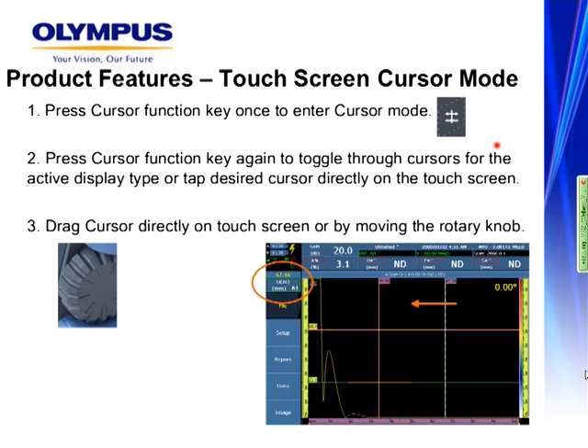In addition to the touchscreen functions, for the active display type, A-scan, S-scan, C-scan, etc., pressing on the cursor function key again toggles through the applicable cursors for that display type, allowing them to be manipulated quickly and easily using the rotator knob and your thumb. The example of this that you see here is the A-scan.